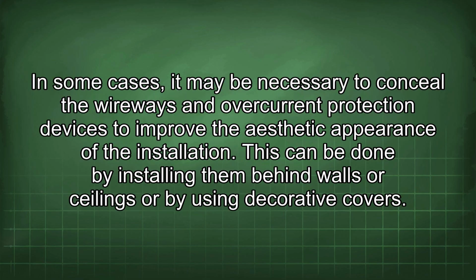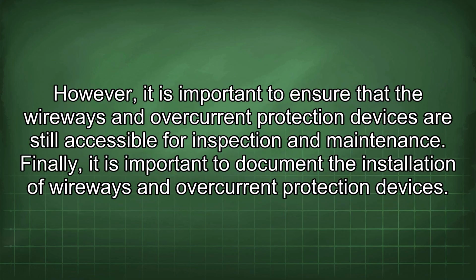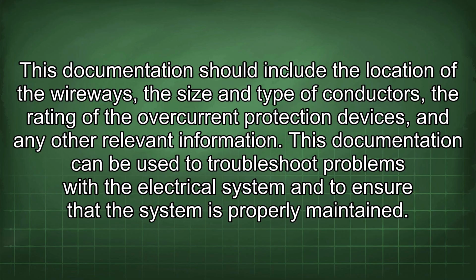In some cases, it may be necessary to conceal the wireways and overcurrent protection devices to improve the aesthetic appearance of the installation. This can be done by installing them behind walls or ceilings or by using decorative covers. However, it is important to ensure that the wireways and overcurrent protection devices are still accessible for inspection and maintenance. Finally, it is important to document the installation of wireways and overcurrent protection devices. This documentation should include the location of the wireways, the size and type of conductors, the rating of the overcurrent protection devices, and any other relevant information.